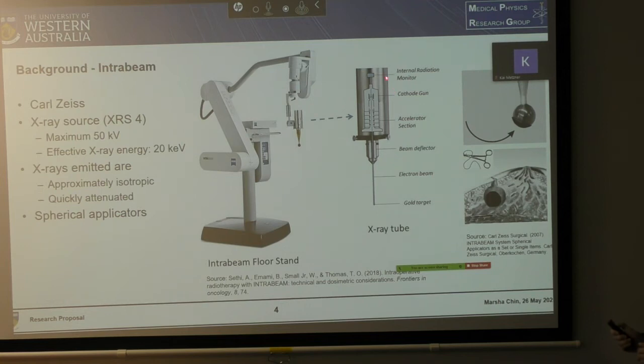You've also got an internal radiation monitor, which measures the dose rate constancy. So if many X-rays scatter back up the drift tube and it reads 10% or more deviation, then it will actually cut off the radiation delivery. You've also got some shields. This is a spherical shield and that's a flat shield. And you can place them on the applicator, so not all the tissues in the patient are irradiated.